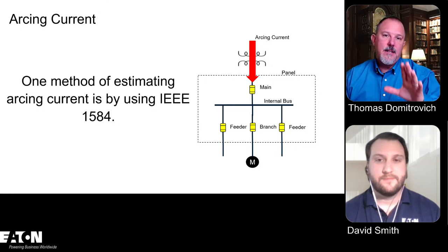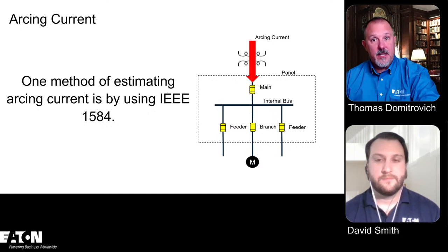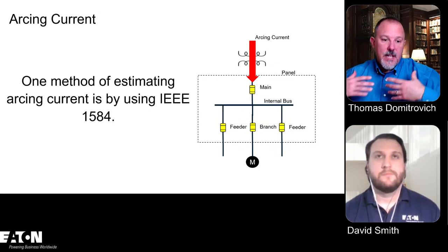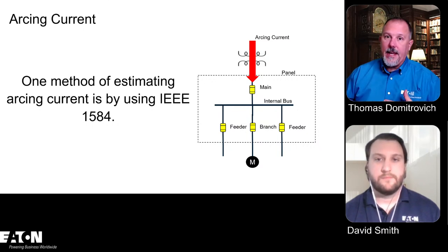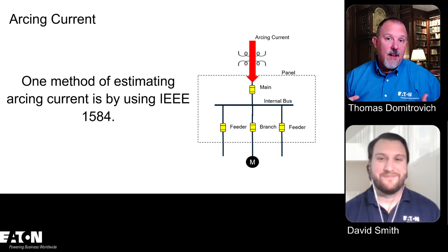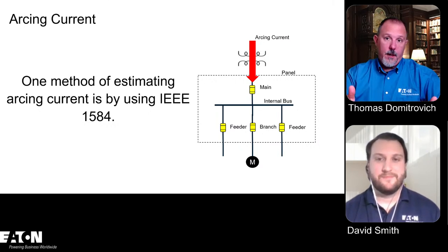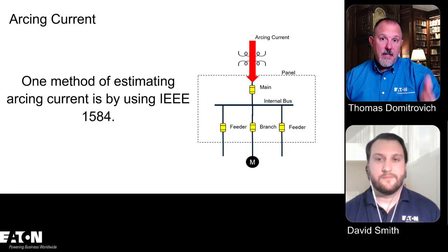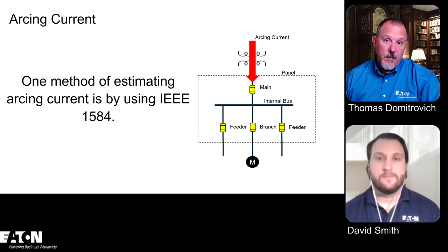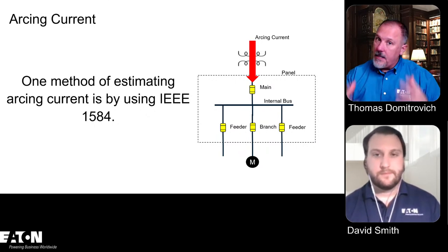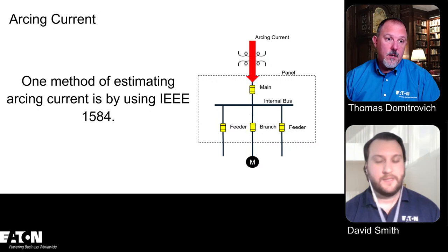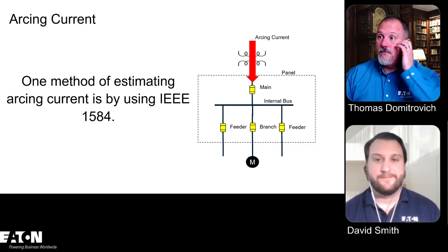And what we learned in that actual case study was that our calculations of incident energy based upon the conditions were higher than what we actually experienced. Those guys were in light personal protective equipment anyway. They weren't in a 40 cal moon suit. They were in an 8 cal outfit, which is the way they dressed. They either dressed 8 or 40. They dressed for 8. They did their work. They had an event. Nobody was injured. Nobody was killed. The equipment didn't have to be reinstalled and updated. We were able to clean it out and get it re-energized very quickly. So that's the whole point. That's why we're here.